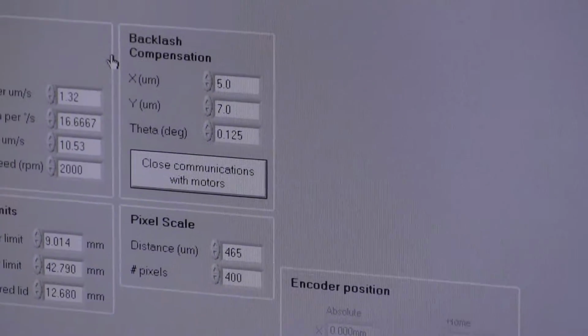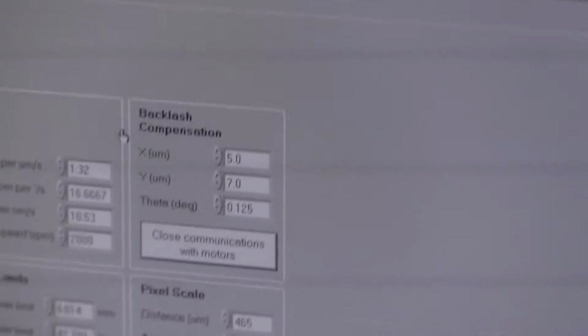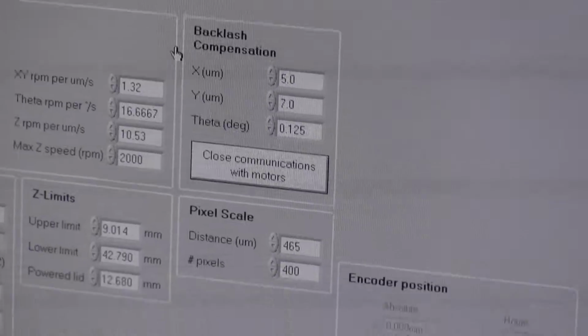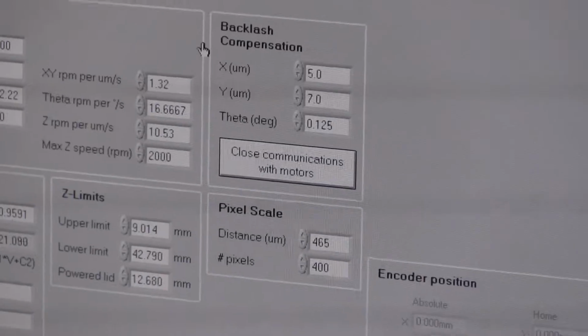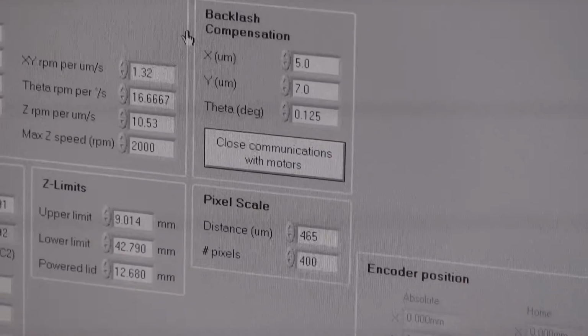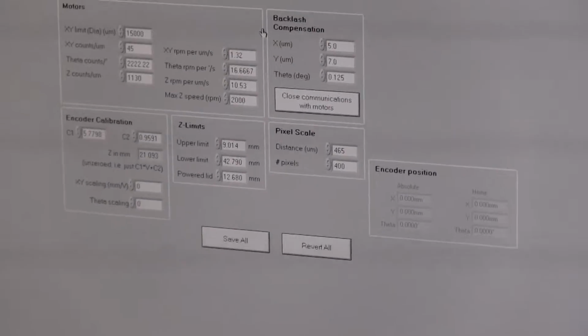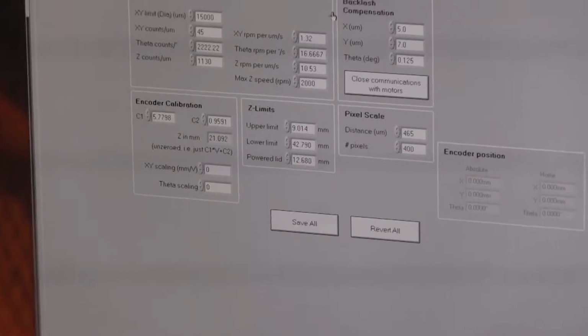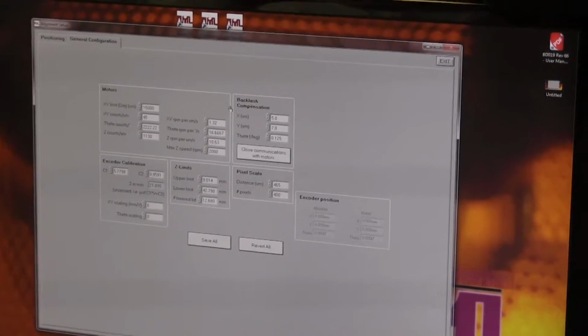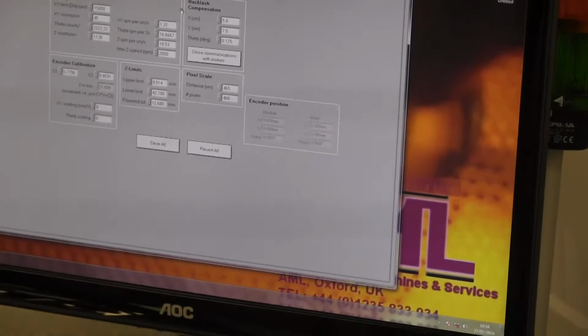We do have an automatic alignment as an option. Now the motors have a certain amount of backlash in them, usually between 5 and 10 microns, and the automatic alignment needs to know what those values are to be able to take up that backlash before it knows that the manipulator is going to start moving. So we put those in anyway, but in this particular case they're not relevant here.